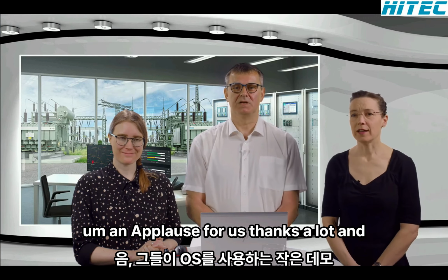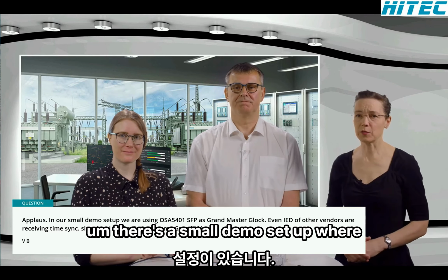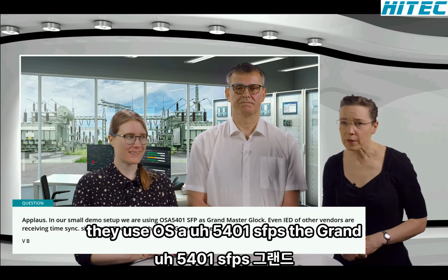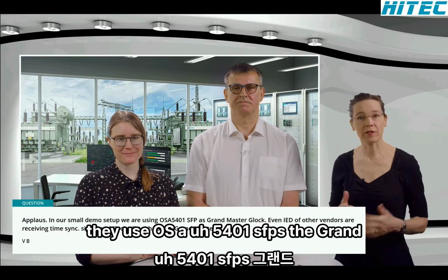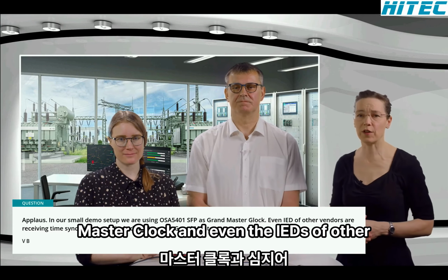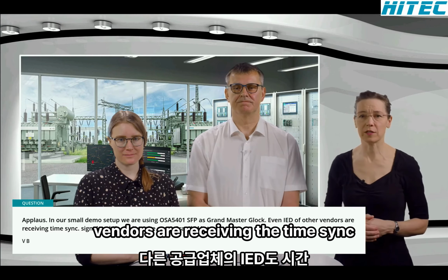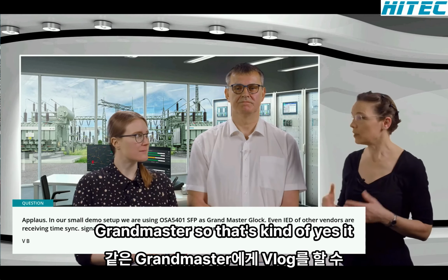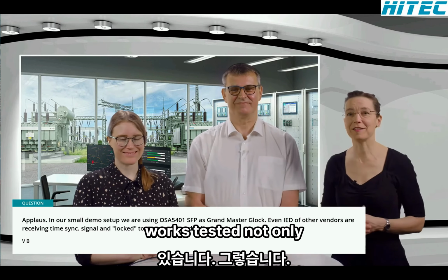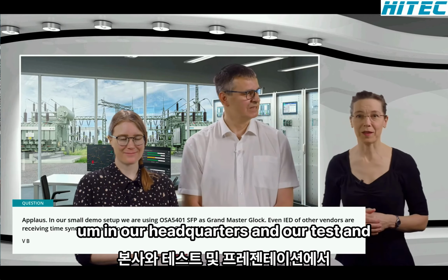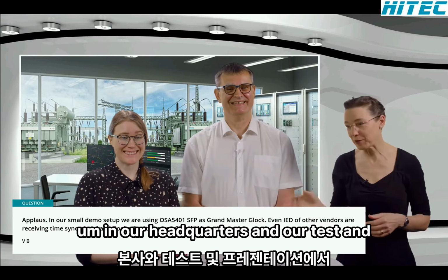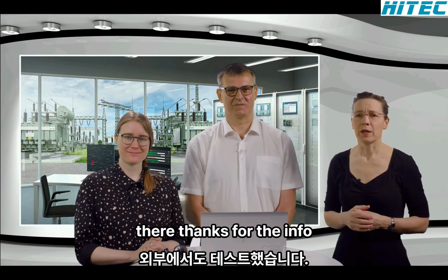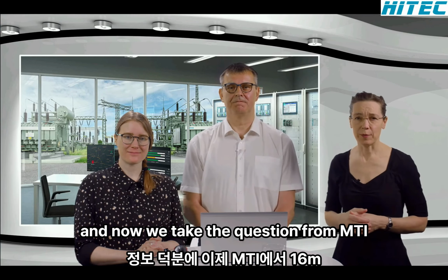All right. Next one is an applause for us. Thanks a lot. And there's a small demo setup where they use the OSA 5401 SFP as the grandmaster clock. And even the IEDs of other vendors are receiving the time sync signal and are locked to the same grandmaster. So yes, it works. Tested not only in our headquarters and our presentation, but also tested out there. Thanks for the info.